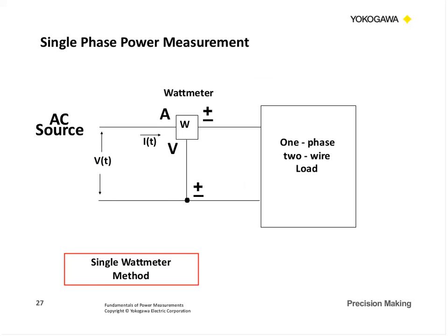So let's make a measurement. Okay, we have some type of a device out here that may be drawing some power. And so this could be a simple single-phase motor, could be some kind of a load, something, we don't care. It's got two wires from the AC source hooked up to the AC line, supplying power to it. We're gonna put our wattmeter in front of this, okay, at the line coming in. We're going to measure the current coming in on that line, and we're going to measure the voltage from line to line.